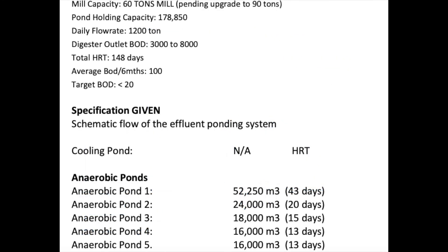In summary, this is a 60-tonne mill with a pond holding capacity of 178,850, a daily flow rate of 1,200 tonnes, total HRT of 148 days, average BOD of 100, and a targeted BOD of 20. From the technical study, an audit report and a customised treatment plan have been sent to the mill.